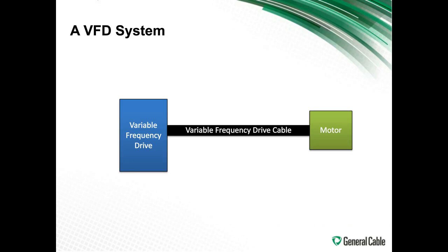To understand how a VFD system works and what parameters need to be considered, let's look at the system. You basically have a variable frequency drive, and you have it control a motor. So between the variable frequency drive and the motor is a cable. That cable is what people don't seem to think about. It is the least considered part of the system, but actually can be a huge component in terms of reliability and the way the system actually works, if some thought is put into it ahead of time.